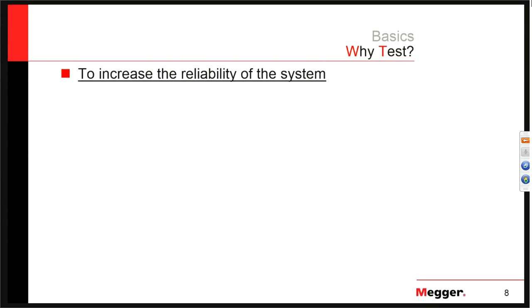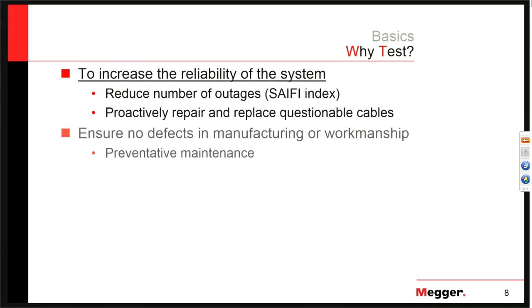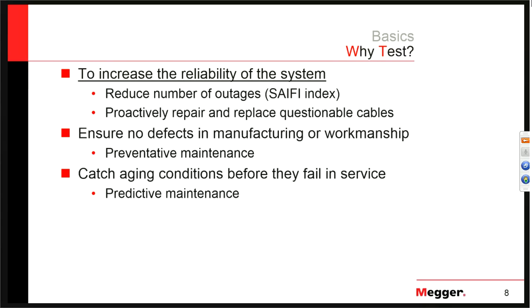Why are we even testing? Ultimately, the goal is to increase the reliability of the system. We're reducing the number of unplanned outages, reducing our SAIFI index, and we're able to proactively repair and replace questionable cables. We can do preventative maintenance, ensure there are no defects in manufacturing or workmanship, prevent faults from occurring in the first place, or predict that a cable is about to fail — trying to catch these aging cases before we suffer an in-service fault.